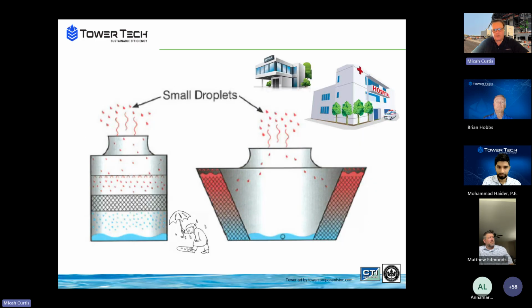So drift rate. The healthcare industry is very sensitive to drift. Drift is the water droplets that are blown out of the cooling tower, either the top or the side, that escape past the drift eliminators. And drift is often something people don't like. It's a consideration, but it's often minimized. I don't want to say it's ignored, but it's often minimized because it is a very small amount of water relative to the evaporation that occurs in the cooling tower. So it's a small amount of water relative to the flow rate through the tower.